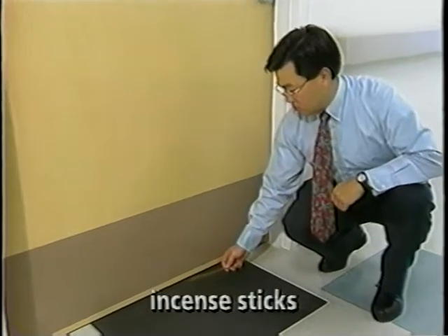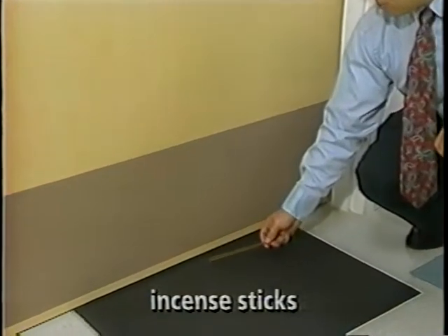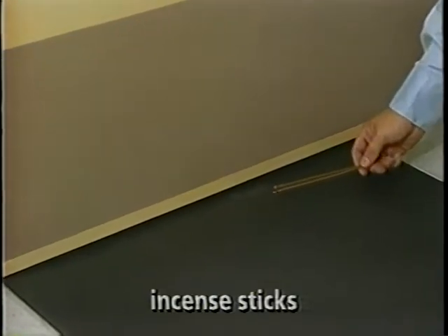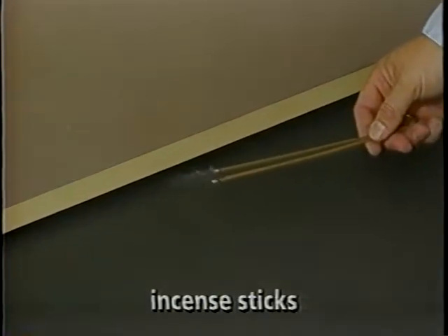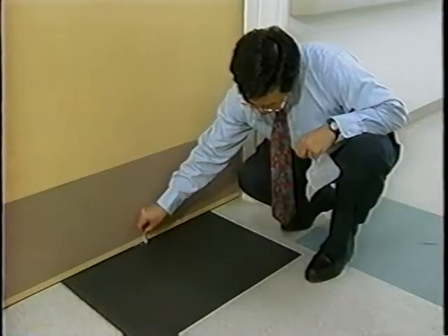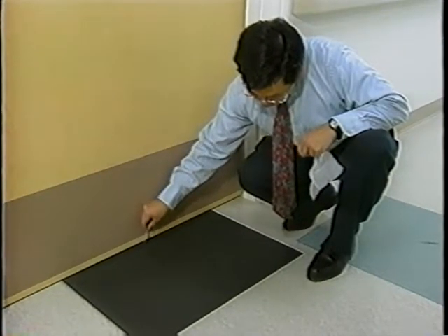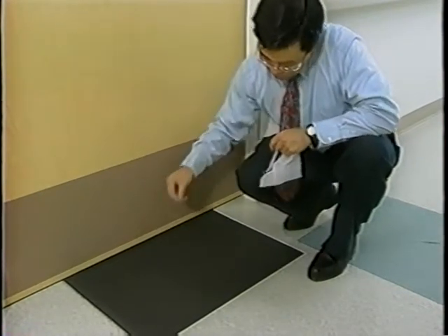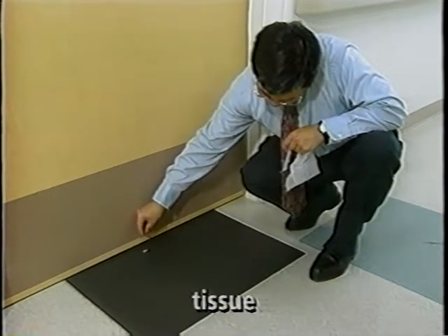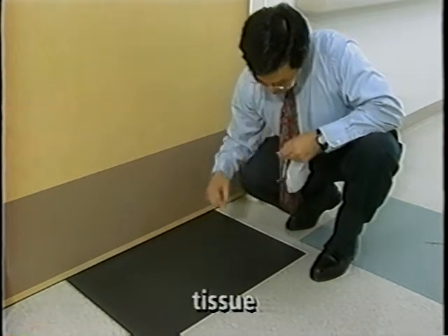If smoke tubes are unavailable, you can use incense sticks to generate a stream of smoke. In this case, we recommend that you use at least 2 sticks. Lastly, you can also confirm negative pressure using a telltale device, which can be something as simple and readily available as a piece of facial tissue.